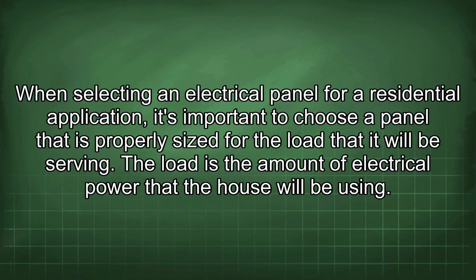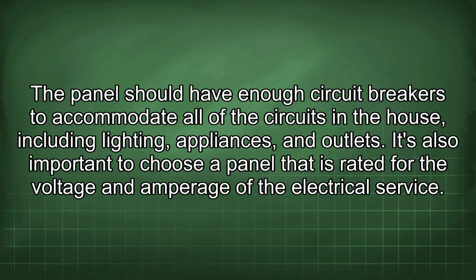When selecting an electrical panel for a residential application, it's important to choose a panel that is properly sized for the load that it will be serving. The load is the amount of electrical power that the house will be using. The panel should have enough circuit breakers to accommodate all of the circuits in the house, including lighting, appliances, and outlets. It's also important to choose a panel that is rated for the voltage and amperage of the electrical service.